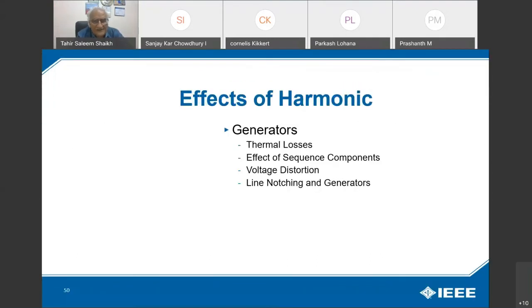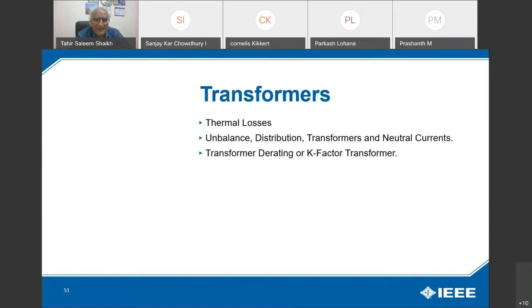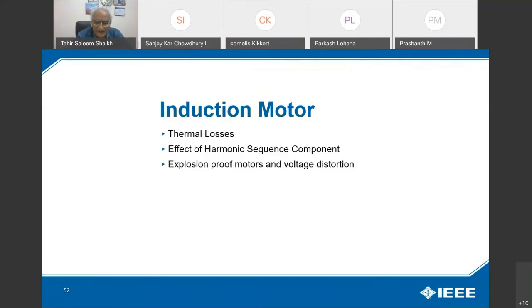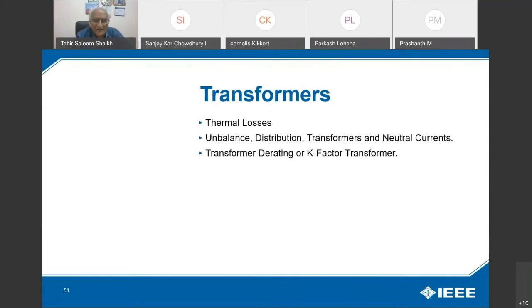In generators, if you are operating generators, there would be thermal losses, effect on sequence components, voltage distortion, and line notching. Transformers will have thermal losses, unbalanced distribution, and transformer neutral current. For selection of a transformer in an environment of harmonic distortion, you have to calculate the K factor. This is called the transformer derating, or K factor for the transformer. If you are ordering a transformer for a harmonic distortion environment, you can do this K factor calculation, find out what the K factor should be, and select your transformer accordingly.